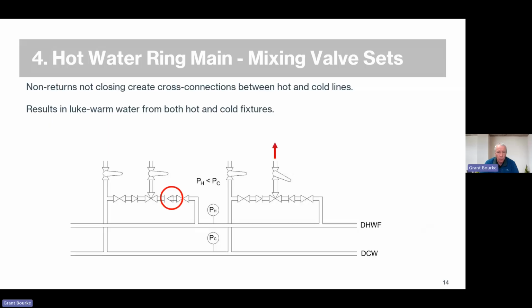I'm now going to turn a hot fixture on the other offtake point, and instantaneously, because I've got more flow from the hot water line than the cold water line, I'm going to have a lower pressure in the hot water ring main than in the cold water delivery line. So I'm going to have more pressure in the cold water side than I have in the hot water side. So this cold is going to sneakily jump across here and get into my domestic hot water line.